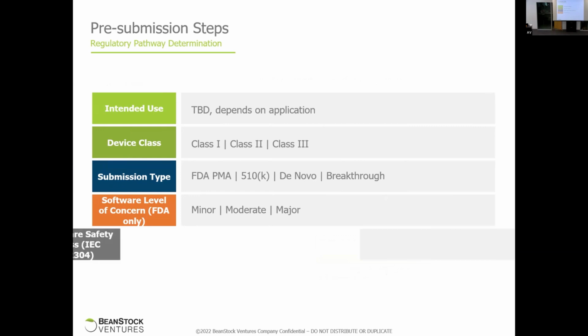So these are things I'd like you to consider when developing your medical device. These are things that should be defined up front, but can be refined iteratively. So intended use: this is going to depend on your application. Your intended use is basically going to be used as input to define your device classification. There are three FDA device classifications: 1, 2, and 3. And then your submission type, which I'll talk about in a second. You have your FDA PMA, 510(k), de novo, and breakthrough.